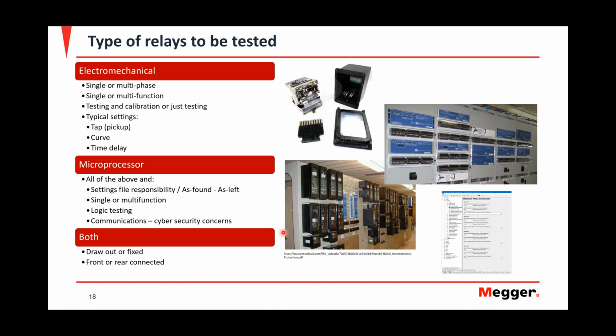In the electromechanical world, it was really easy. You just pull the test switches down and you pull the relay out, and the gear could stay powered up. There are some electromechanical relays that you could draw out too, and the gear doesn't have to be shut down. Or if they're fixed, then, hey, does the customer know that I have to shut down the gear in order to test these relays? If they have test switches, you could isolate it, but they will have no protection. Things like that are questions that you have to ask, because a lot of people don't know that this has to happen.